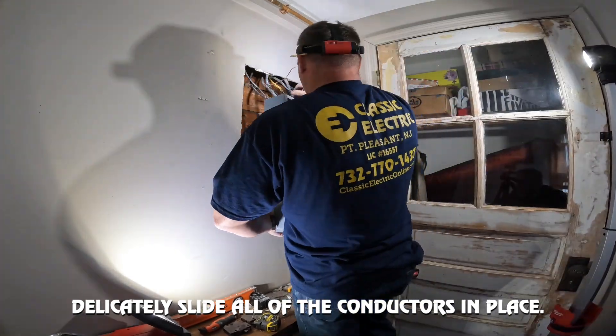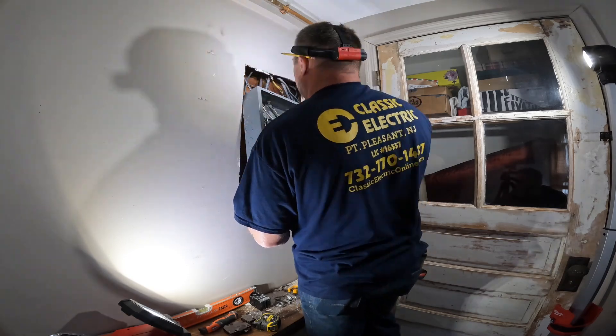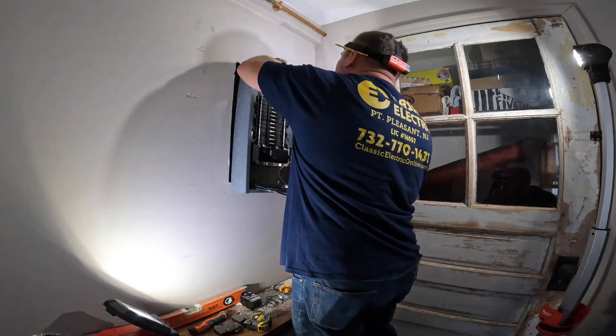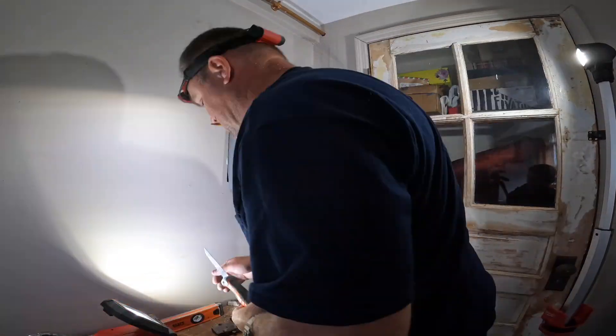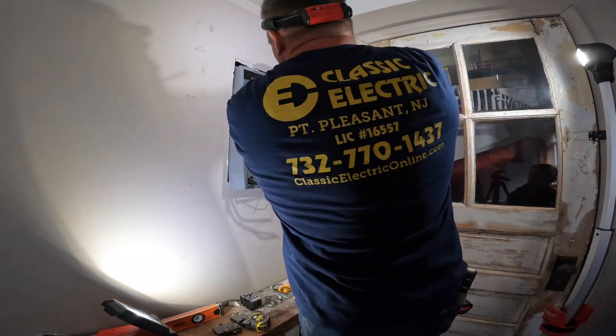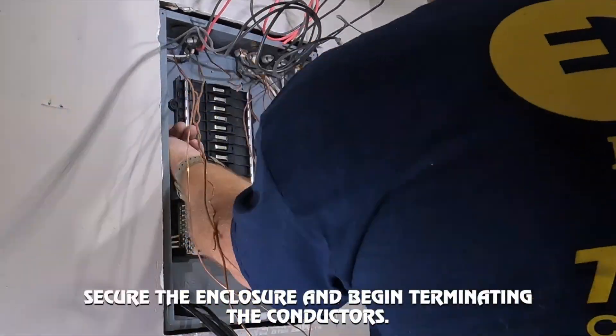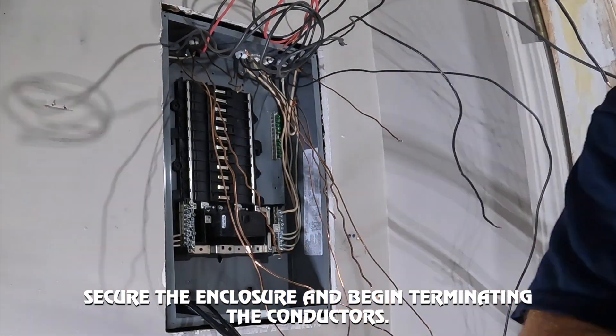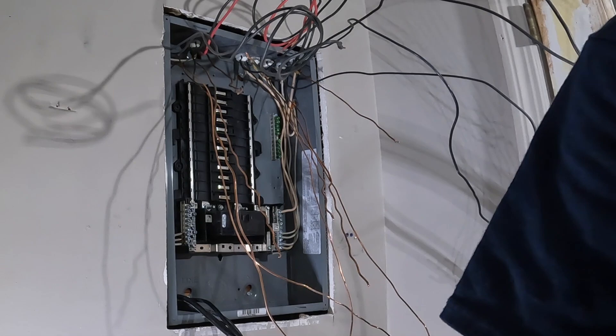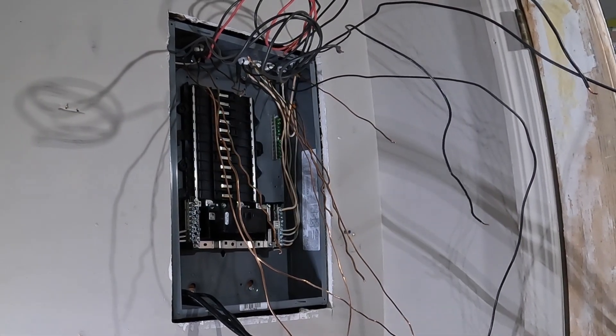Fortunately, like I said, the four-wire feeder was there, so I'm able to isolate the grounds and neutrals. Now this was a job - Brian is a friend of mine, this is his house and he supplied the panel. So I'm just there putting in the work and using the panel that he gave me. He gave me a main breaker panel, which is fine, but this still technically is not the main disconnect. So we left the main breaker in place and we went ahead and isolated the grounds and neutrals as required by the code.